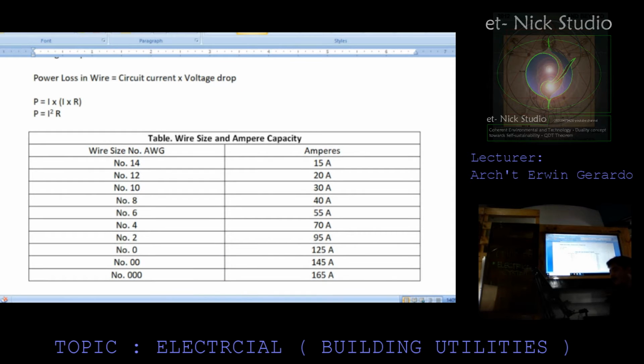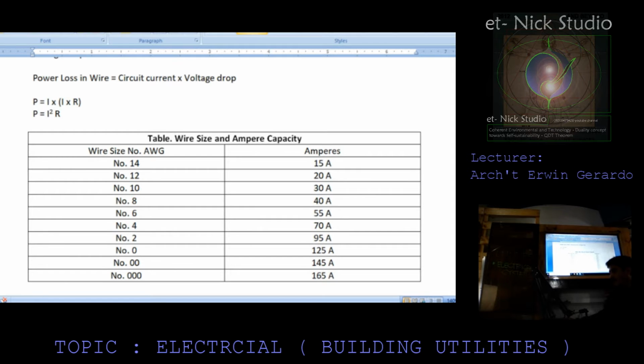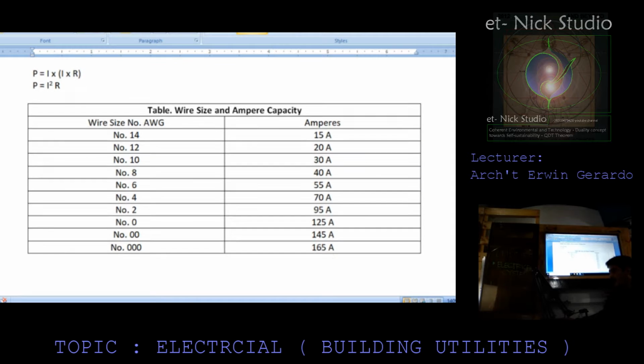This is the table for wire size and ampere capacity. We have here the American wire gauge, having wire sizes of number 14, which can carry 15 amperes. Number 12 can carry 20 amperes. Number 10 can carry 30 amperes. Number 8 can carry 40 amperes. Number 6 can carry 55 amperes. Number 4 can carry 70 amperes. Number 2 can carry 95 amperes. Number 0 can carry 125 amperes. Number 00 can carry 145 amperes. And number 000 can carry 165 amperes.